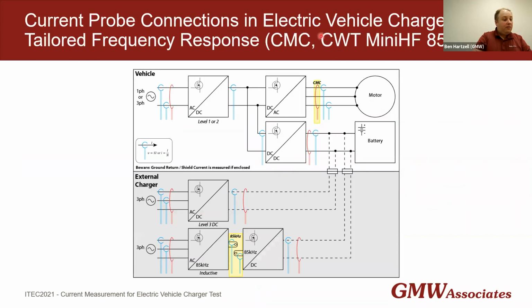And you can see here where it would be used most likely is doing the common mode current between the motor drive and the motor. Here we have three-phase current from the drive to the motor. The frequencies can be near DC, particularly for an electric vehicle, and the differential current of all three should be zero. The CMC lower frequency cutoff, the 2 to 20 kilohertz range, is enough to attenuate the fundamental drive current. However, if there is high voltage switching here in the drive, it may induce high frequency currents, which we want to measure. These high frequency currents could then reach through the motor bearings and lubricant to ground, ultimately breaking down the lubricant.